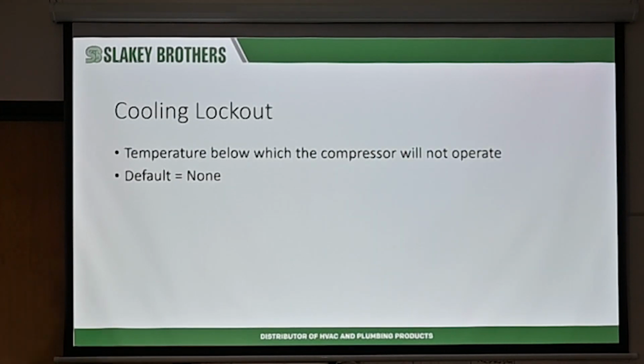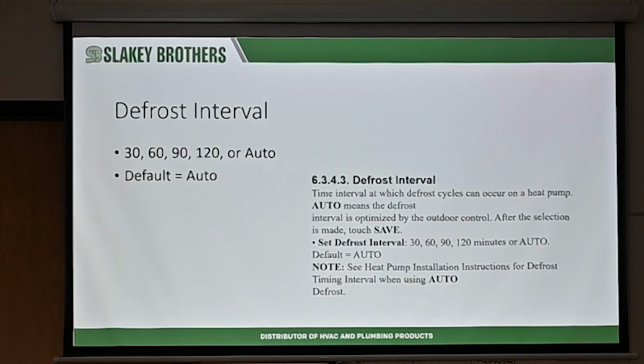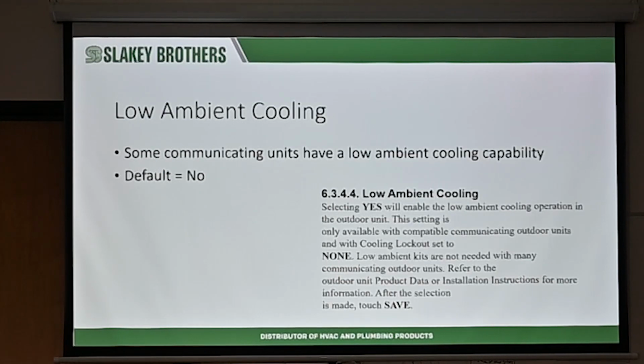Actually, that's a good one for, say it's a business and they're sharing a split system. The owner of the building says, nope, no air conditioning, and once it gets this cold, you can do that for them as well. Defrost intervals, default is auto. Let the unit do it itself. You never have to mess with that. It'll work just fine all on its own. Again, low ambient cooling, if you turn it on, it won't harm anything. If they never use it, nothing ever goes wrong.